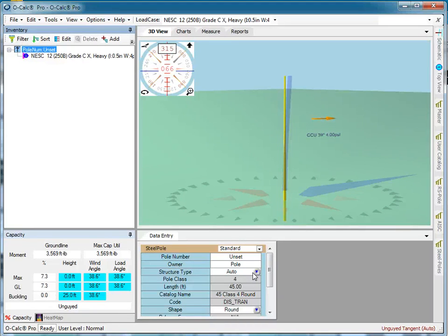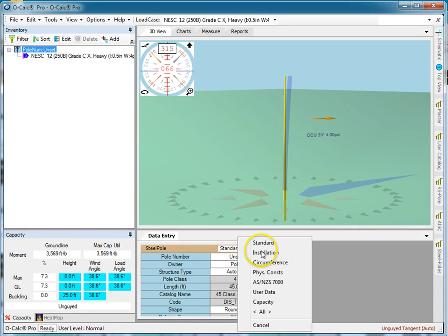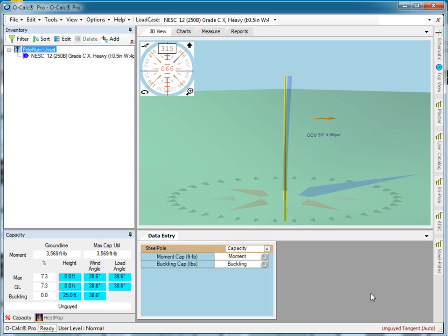here the capabilities of the pole are modeled based on what the manufacturer actually tells you from testing and design that this pole is able to take. So let's take a look at the capacity. And there is both a buckling capacity and a moment capacity, and these are of course combined using superposition when you're doing analysis of the pole.